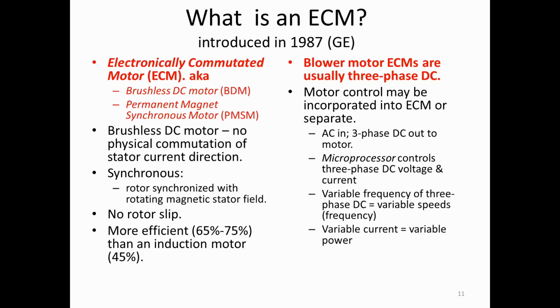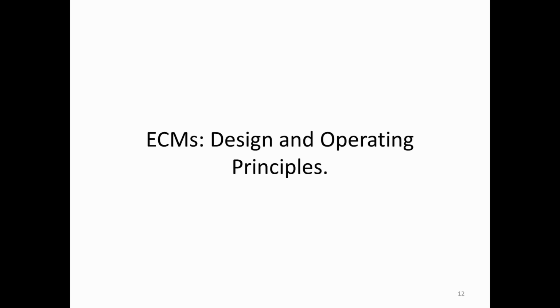The blower motors for ECMs are usually 3-phase DC, not 3-phase AC, which most EEs are familiar with, but 3-phase DC. And the motor control unit, which always uses a microprocessor, can either be incorporated into an ECM or it can be a separate unit with a wire harness or cable leading to the controller. So basically you have, in the case of mine and others, 120-volt single-phase AC in, 3-phase DC out to the motor. The microprocessor controls the 3-phase DC voltage and current, and the motor has variable frequency speeds. So what are these and how do they work and why are they problematic?